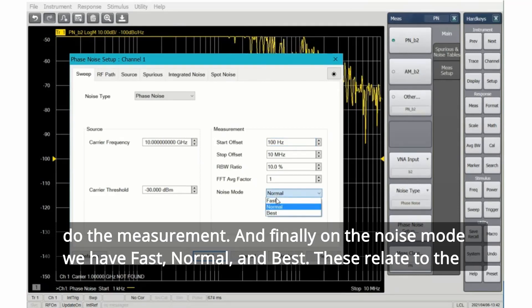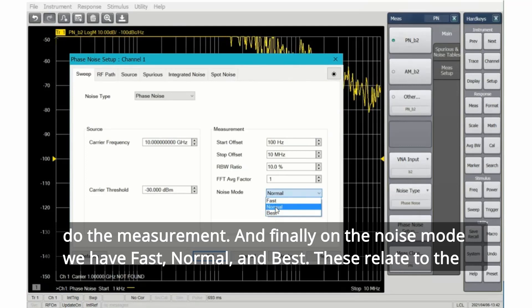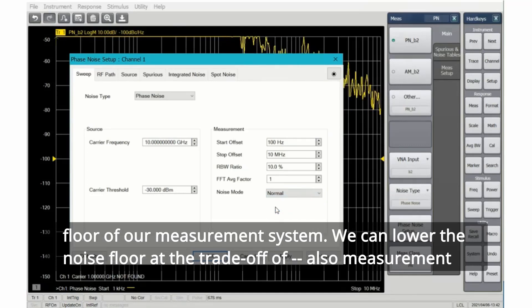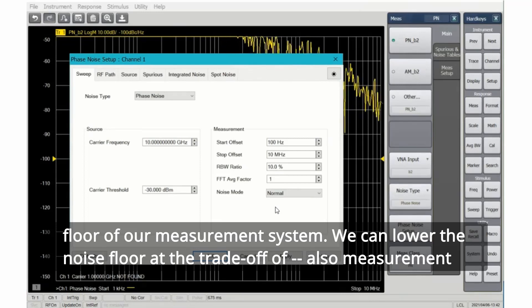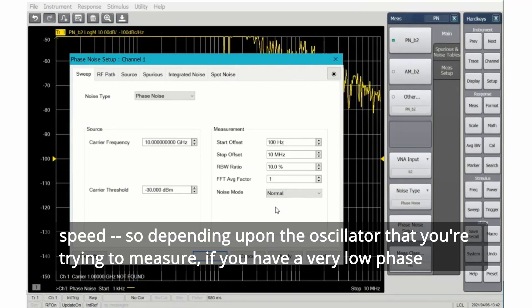And finally, under the noise mode, we have fast, normal, and best. These relate to the floor of our measurement system. We can lower the noise floor at the tradeoff of also measurement speed.